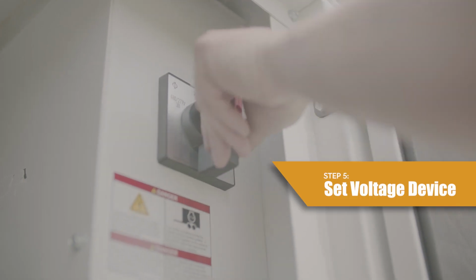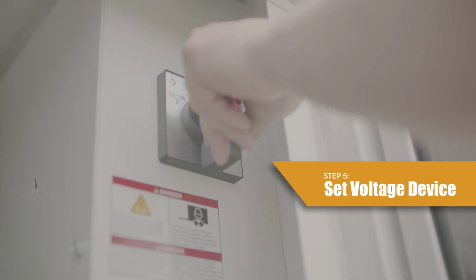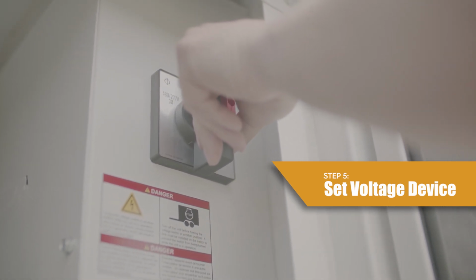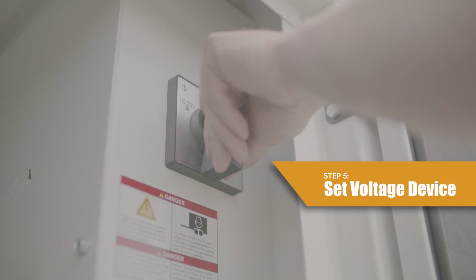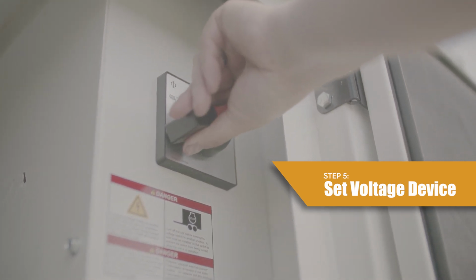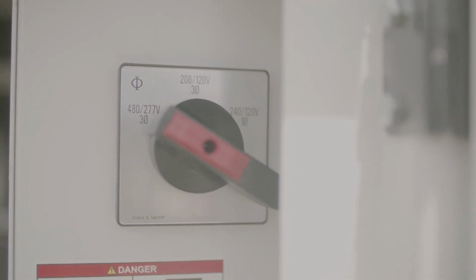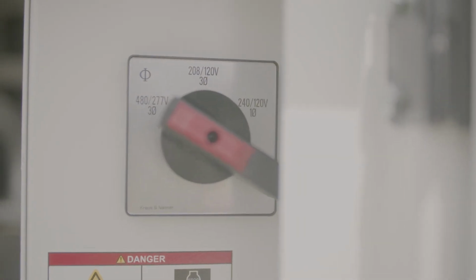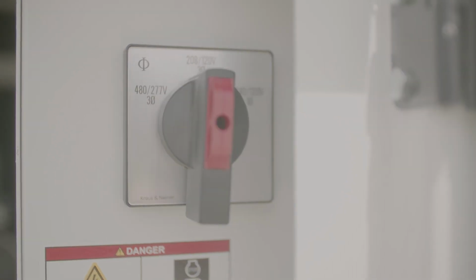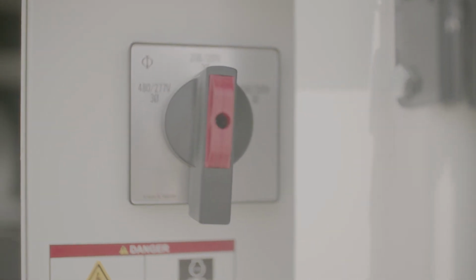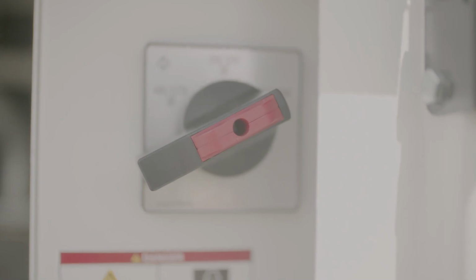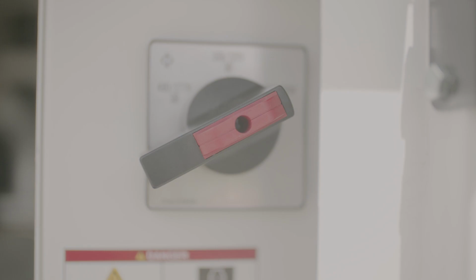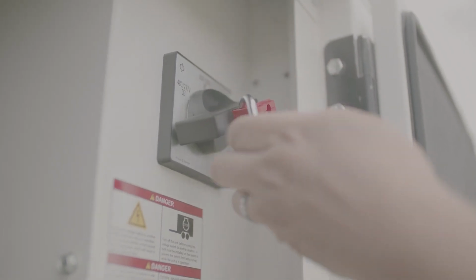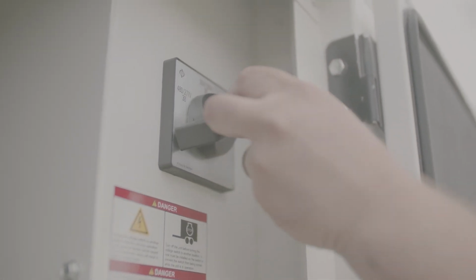Step 5. Set the voltage change device by turning the switch to the desired position. This switch is used to set the voltage for the outlet panel, the connection lug plate, and the cam locks if they are equipped. Turn the switch all the way to the left for the 480/277 volt 3-phase setting. Turn the switch to the middle for the 208/120 volt 3-phase setting. Turn the switch all the way to the right for the 240/120 volt single-phase setting. When the voltage selection is completed, lock the voltage selector switch in the new position.